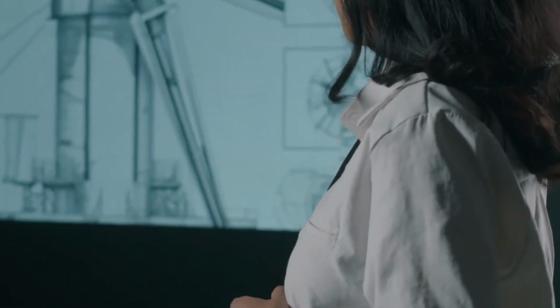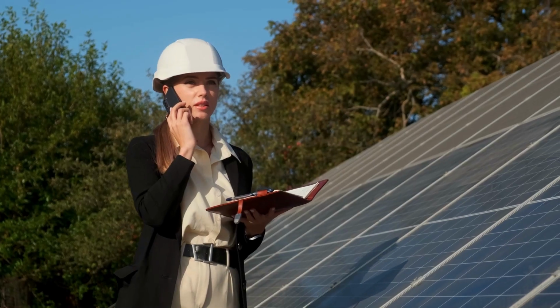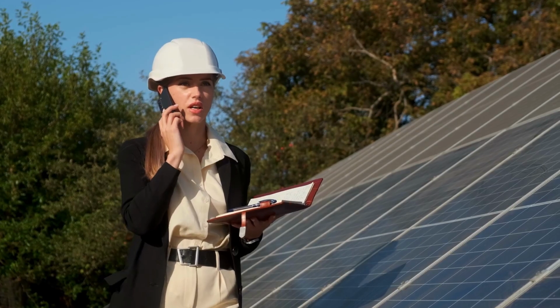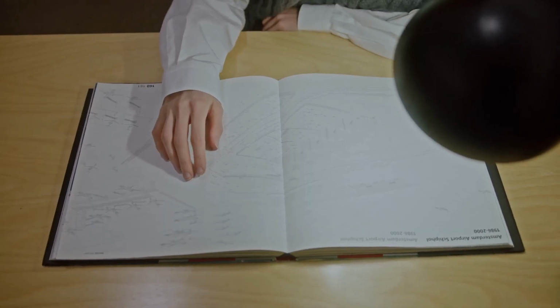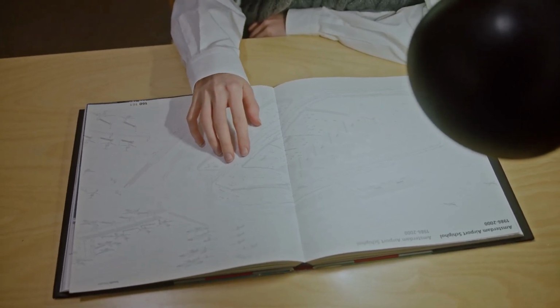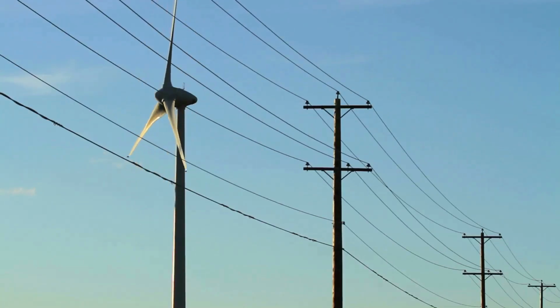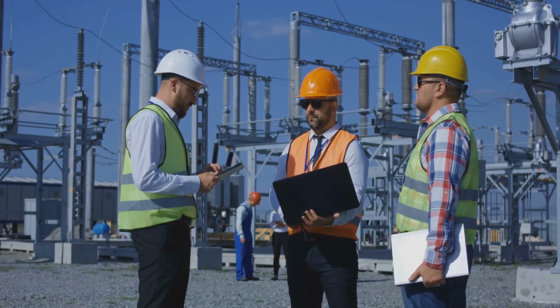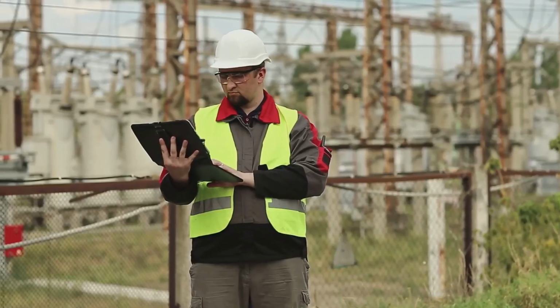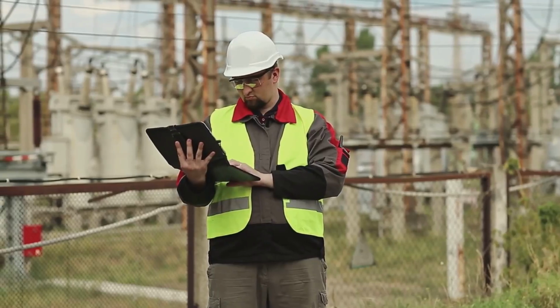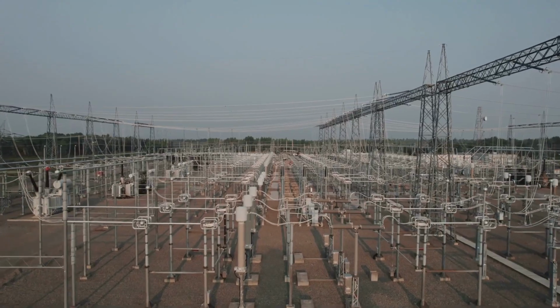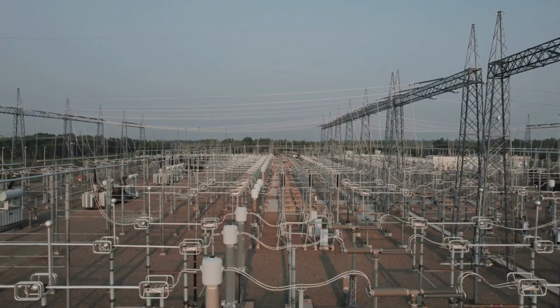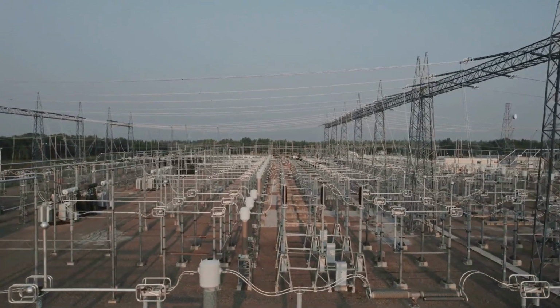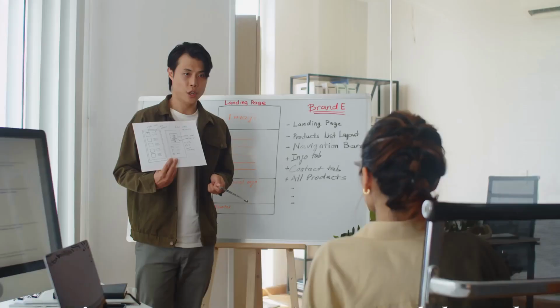Welcome to the beginning of our in-depth training series on IEEE Standard 1547-2018, where our goal is to connect technical standards to real-world operational resilience. I'm Reza Kandezi, and this module focuses specifically on Sections 1 and 4, laying the groundwork for how distributed energy resources, or DERs, should interconnect with electric power systems. But rather than just review these sections at face value, we're going to take a deeper approach, viewing them through the lens of fault ride-through: the ability of a DER to stay online and help stabilize the grid during electrical faults, such as voltage dips, frequency excursions, or transient events.